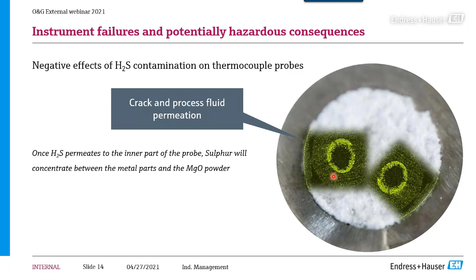Here are some pictures with colors showing the percentage in weight of these elements. In this case, the sulfur: the more yellow it is, the higher the sulfur content in percentage. You can see a lot of sulfur around the minus and plus wires of the thermocouple, very strange, and also near the metal part, also very strange. And then some sulfur inside the magnesium oxide powder.